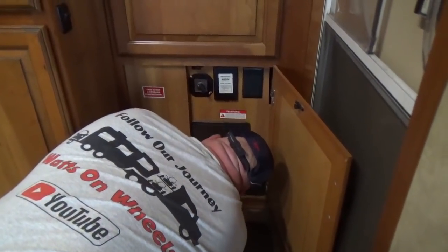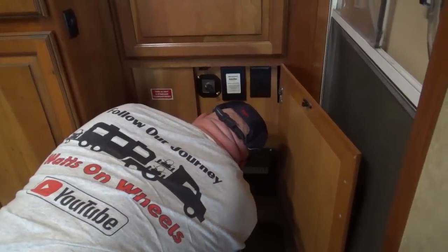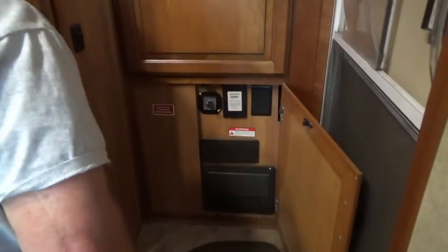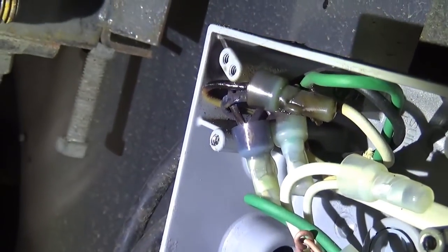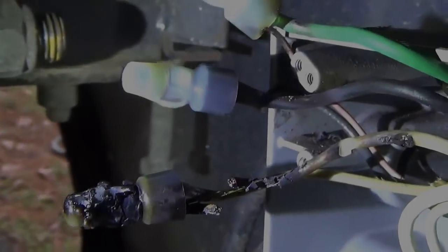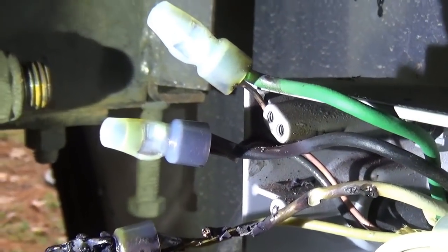We thought we had it figured out, but Dave just shut the fireplace off and the breaker popped — and keeps popping. There must be some bad ones elsewhere. After I repaired the first box, the breaker kept popping, so I knew there was somewhere else down the line. I tracked the wire to the next box and opened it up — and look what I found. I opened up box number two and you can see right there is a fried wire at the top. Same animal as the other box — that is what happens when you use these cinch caps.